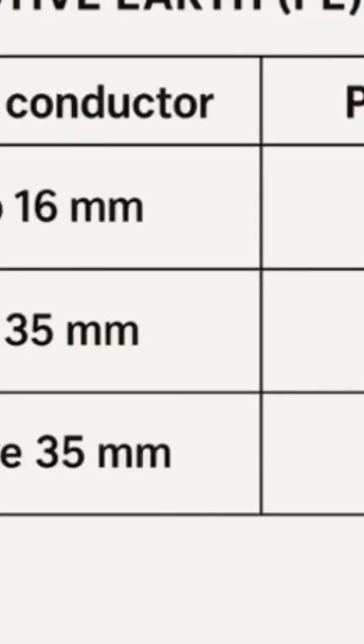Hi guys, I just want to go through a quick brief discussion on earthing conductor thicknesses in South Africa. The standard states that we are allowed to use a one-to-one ratio up until 16 millimeters squared. From 16 to 35 we use 16 millimeters squared, and then from 35 and up we use a 1 to 0.5 ratio, meaning that if your phase conductor is say 70 millimeters squared, then you use a 35 millimeter earth.